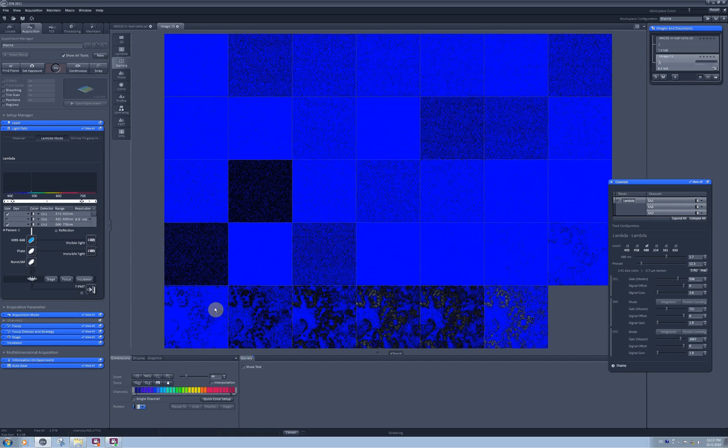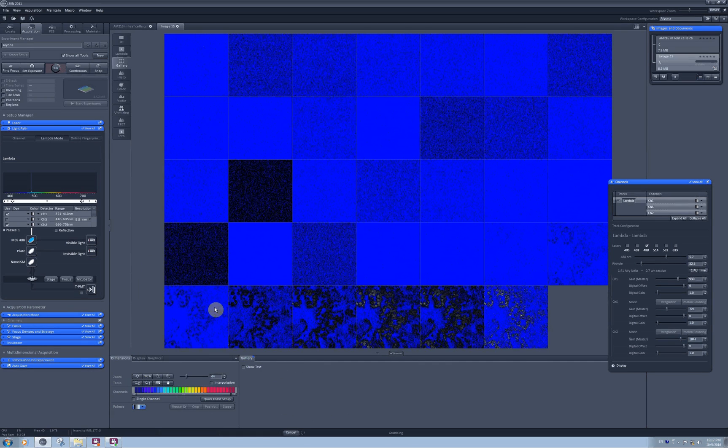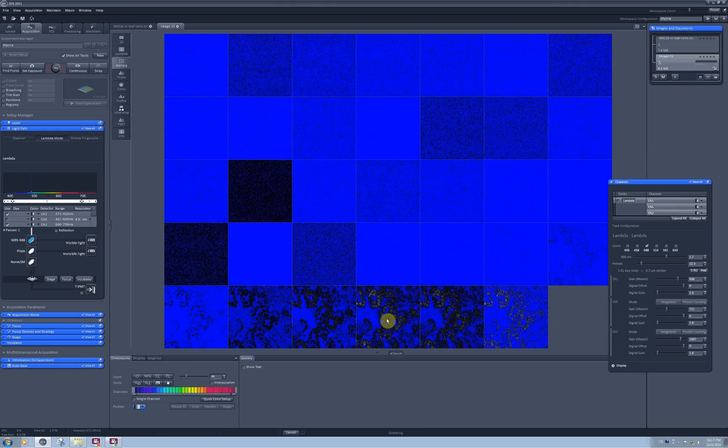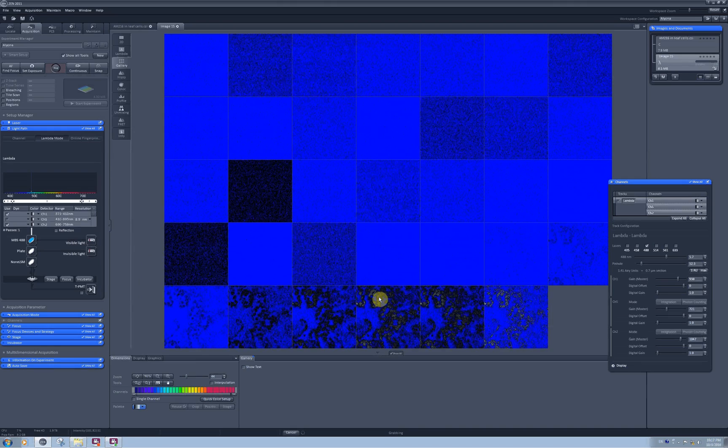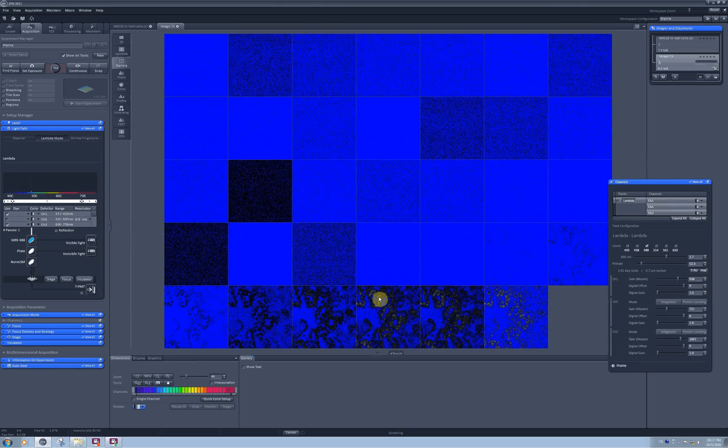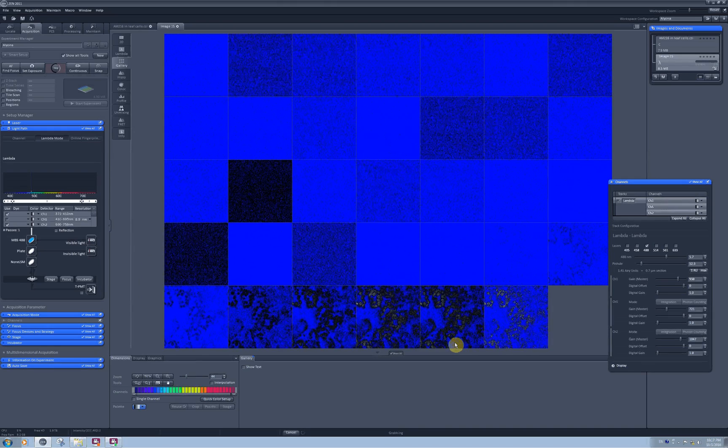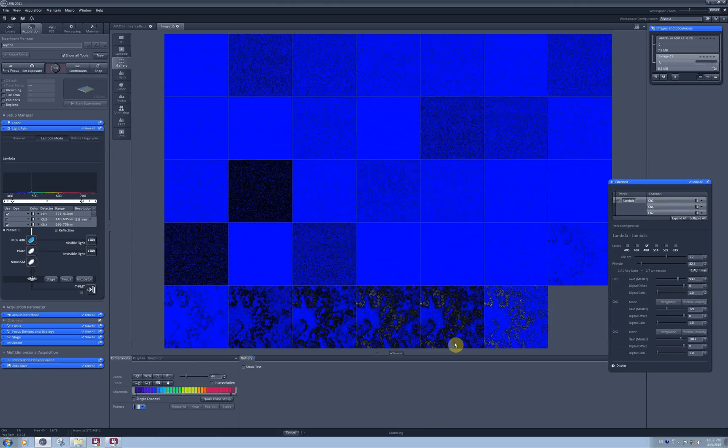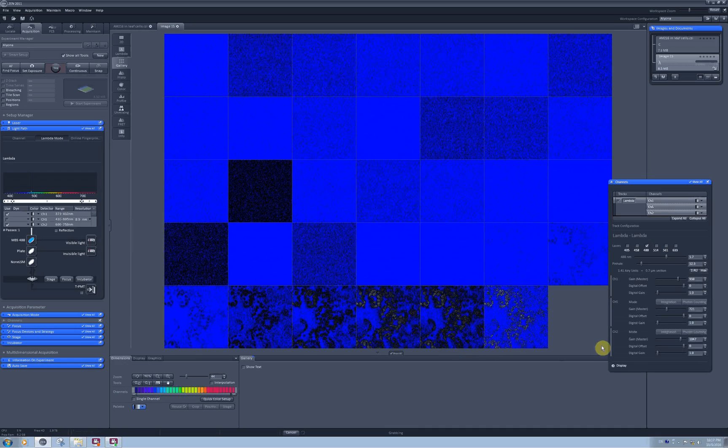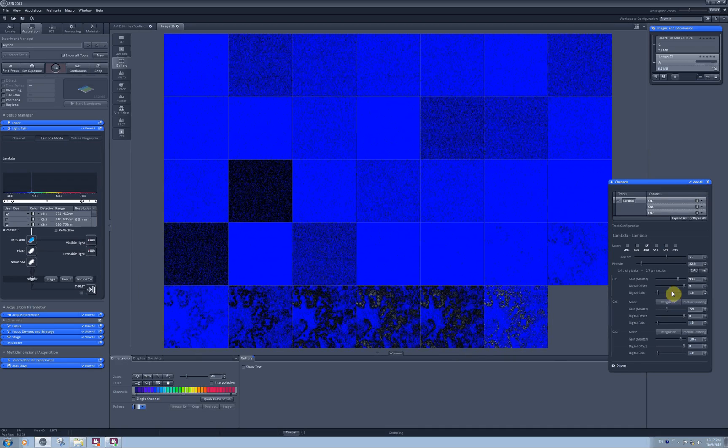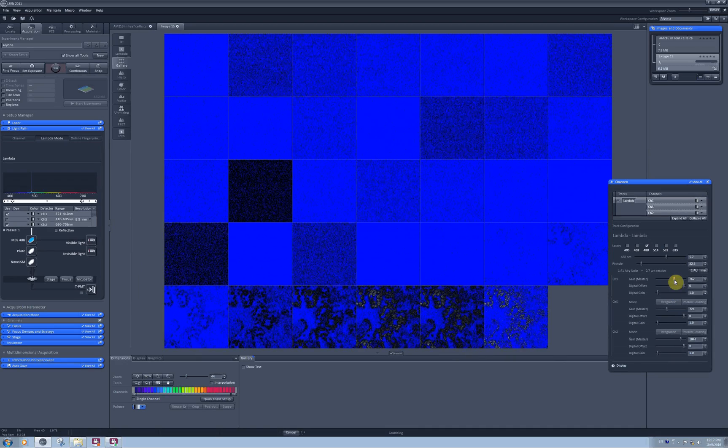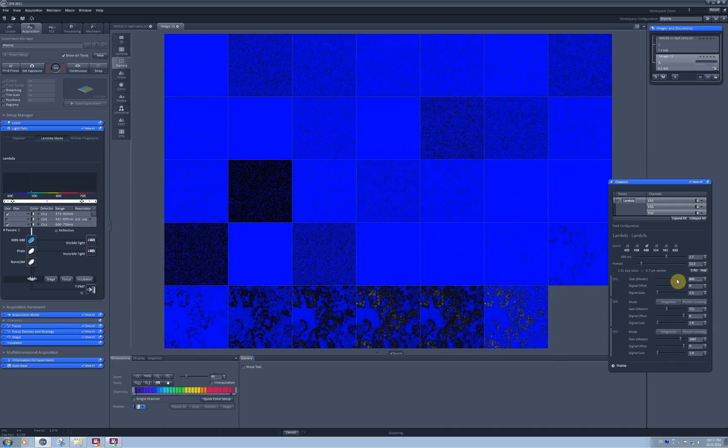Pixels invisible to detector will be coded in the blue color, grayscale pixels have quantifiable intensity and pixels shown with red color are oversaturated pixels. I have three detectors and I need to adjust master gain for each of them.